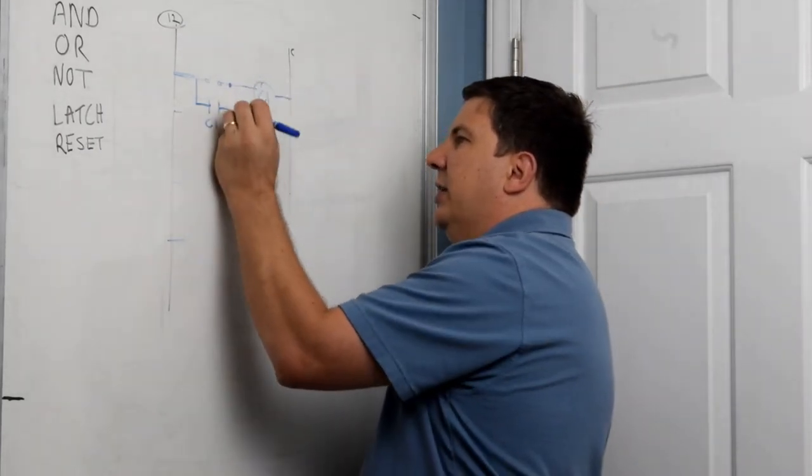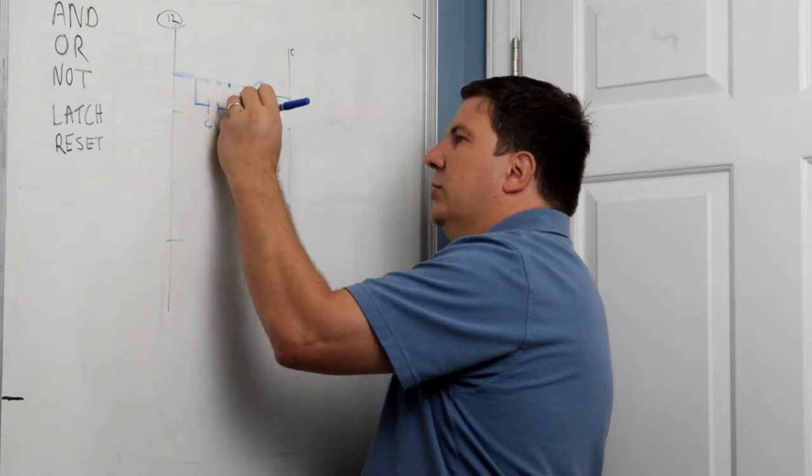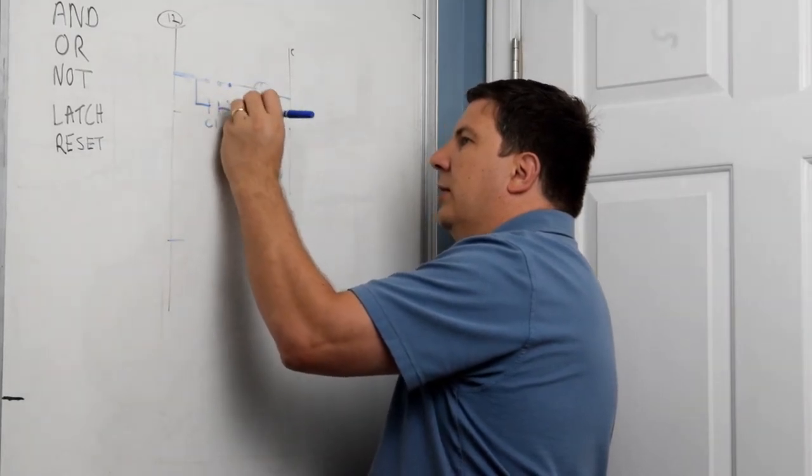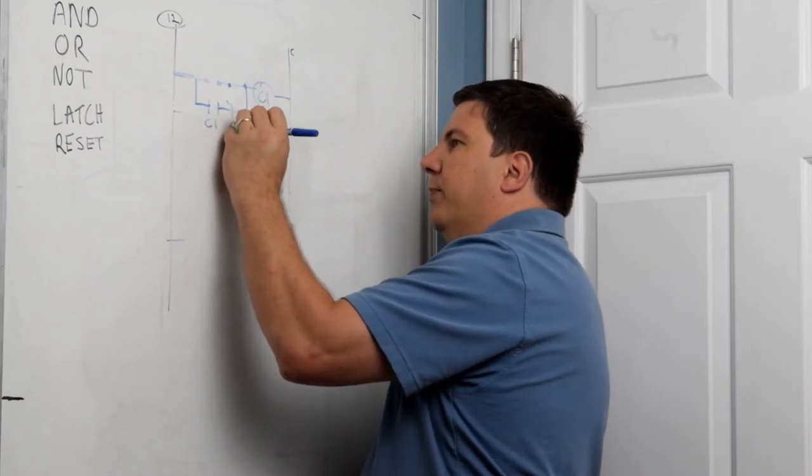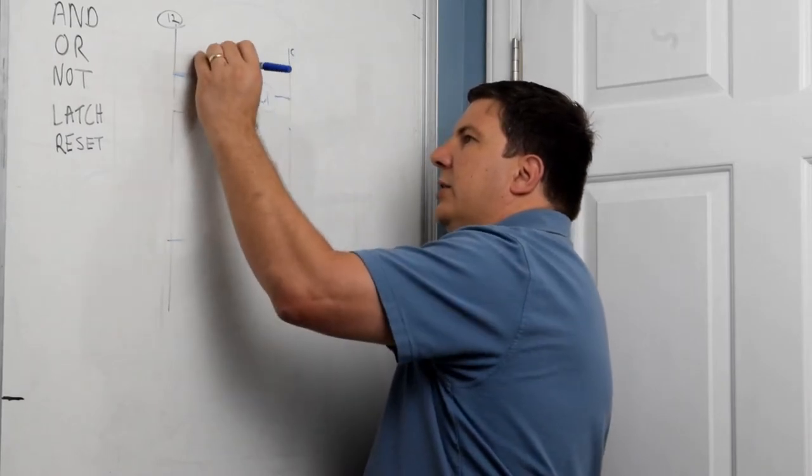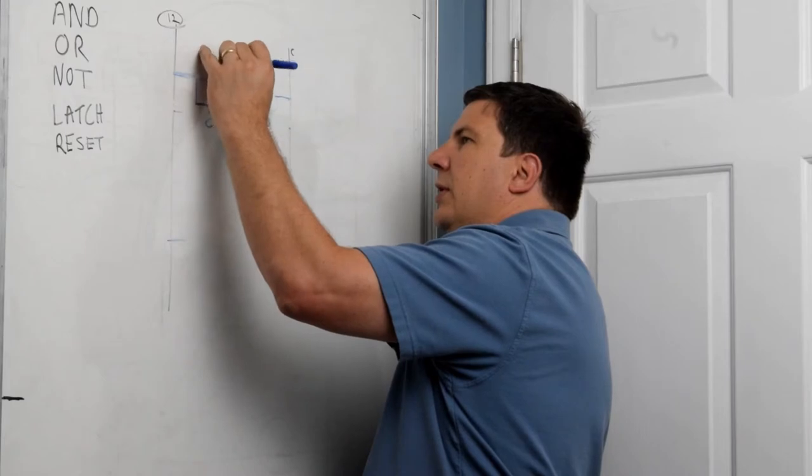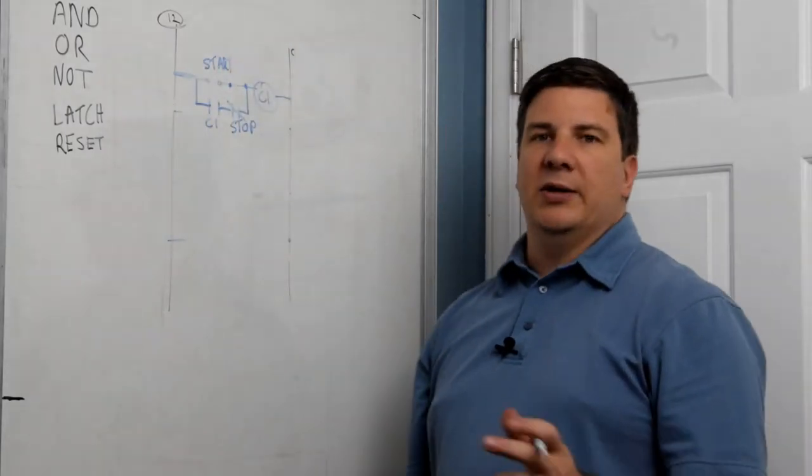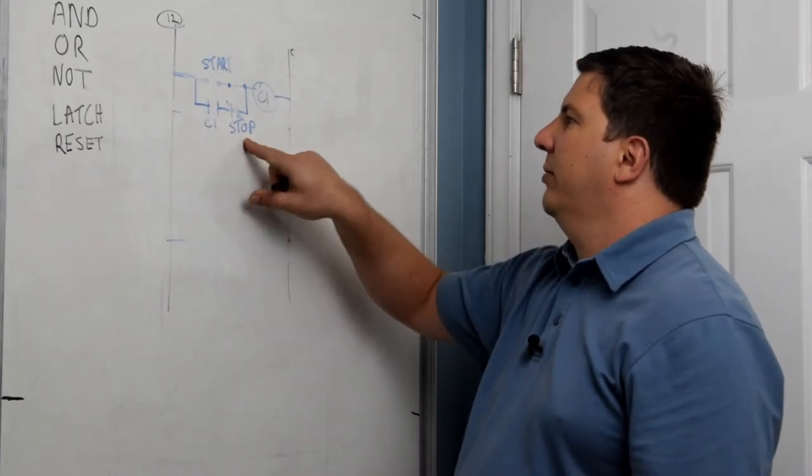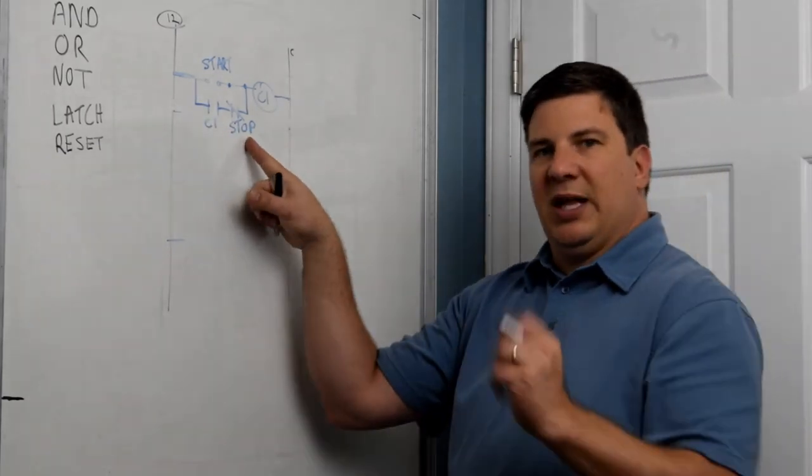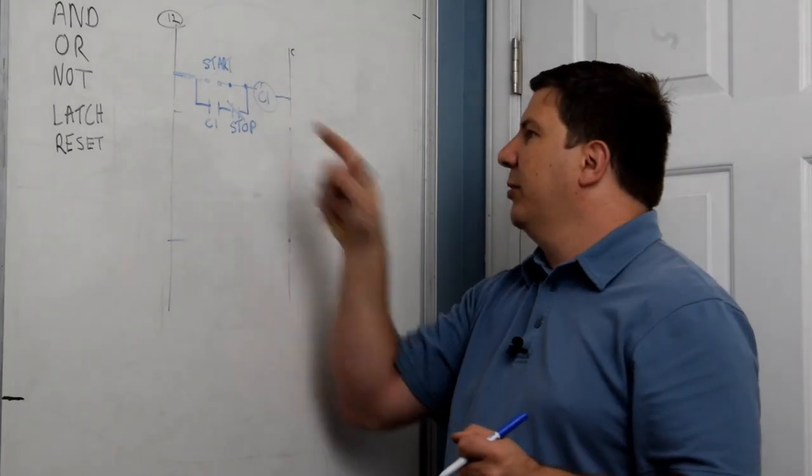So I'm going to take this off right here. I'm going to put a normally closed right there and that's going to be my stop and start. That's how I do it. I'm latching with C1 and I'm using my stop to interrupt that latch to stop the motor.